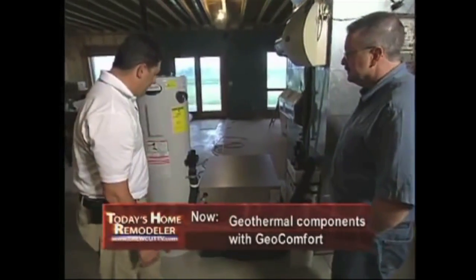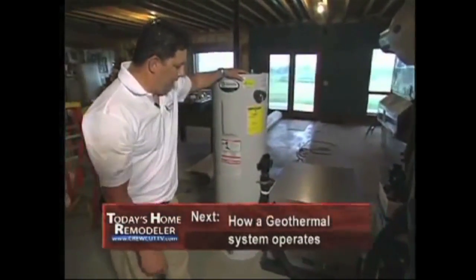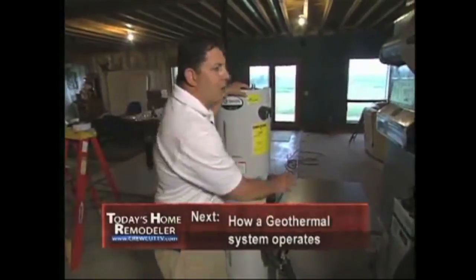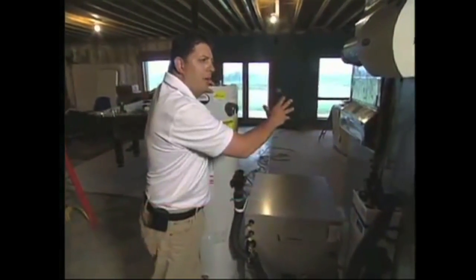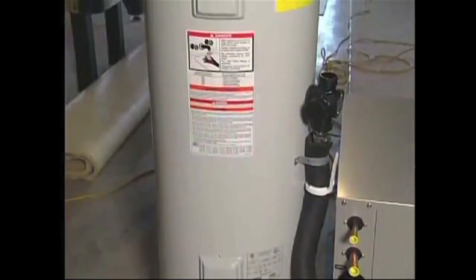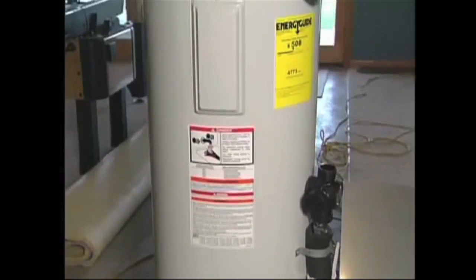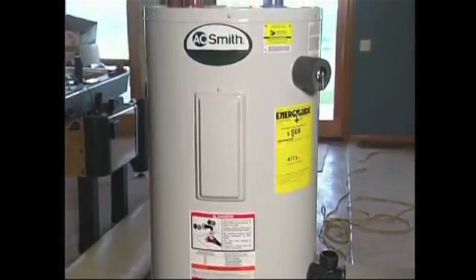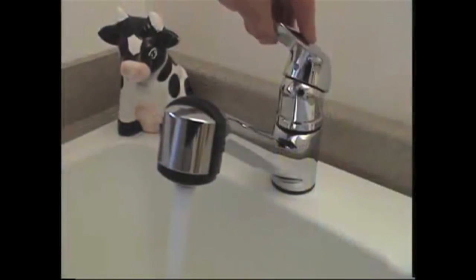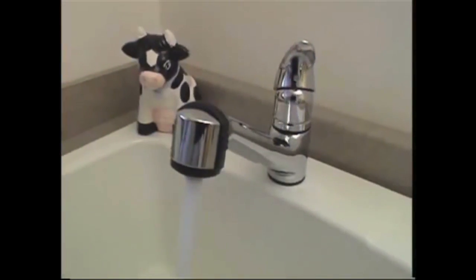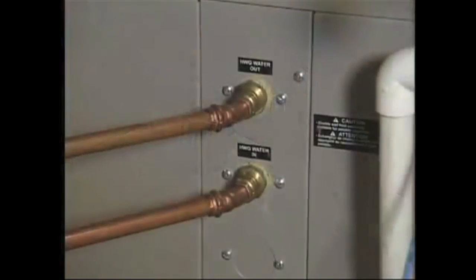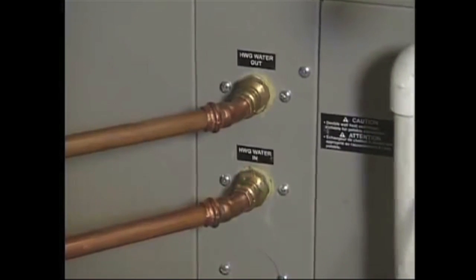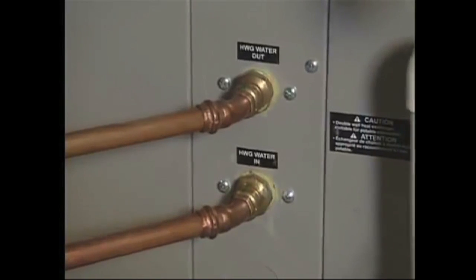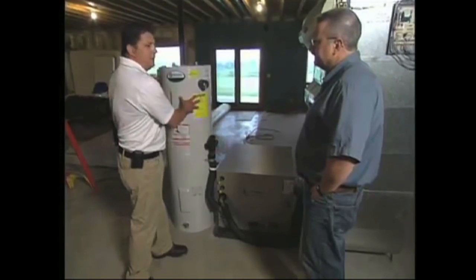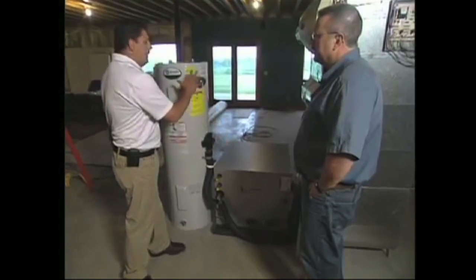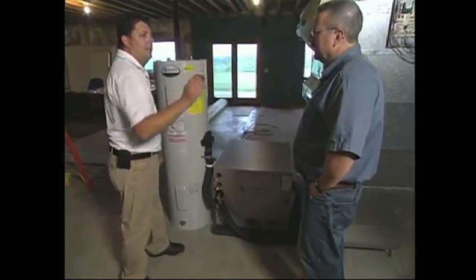Yep, exactly right. And here we've got a preheat tank. Anytime we're operating this system, heating or cooling the home, we're generating hot water into this tank that helps with their domestic water use, so their gas system doesn't run as much. Is this a more efficient way of doing it? Yeah, we could take it right to the gas water heater, but because the gas water heater recovers so quickly, you won't get the full benefit of the hot water generator. So we put a preheat tank in, and anytime this is running it heats this tank at its own free will, storing it here, which then tops off the existing water heater.